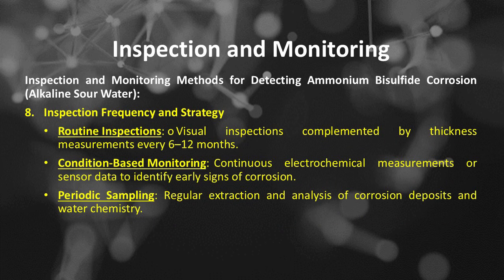Inspection and monitoring methods. Number 8 is inspection frequency and strategy, which includes routine inspections, visual inspections complemented by thickness measurements every 6 to 12 months; condition-based monitoring, using continuous electrochemical measurements or sensor data to identify early signs of corrosion; and periodic sampling, regular extraction and analysis of corrosion deposits and water chemistry.